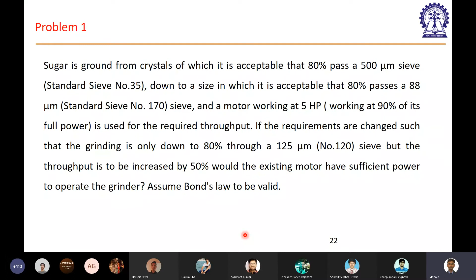Now what can we conclude? In the question it is written that the motor is working at 90% of its full power. Would it be 5 into 0.9 in the place of E1? No, the motor is working at 5 horsepower. In bracket it is written that this 5 horsepower is working at 90% of its full power. So 90% of its full power is 5 horsepower. Oh, got it, sir. Yes. The motor is working at 5 horsepower, which is 90% of its full power. Now the ultimate question is, would the existing motor have sufficient power to operate?